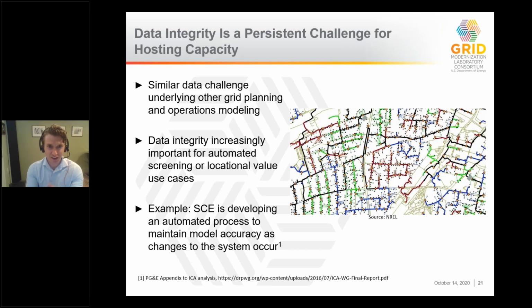I just want to flag how data integrity is really a persistent challenge for hosting capacity. This is similar to ADMS adoption or other systems that really rely on the system data being available and accurate. But as we think about the more advanced use cases of actually approving interconnection applications based on an automated method that maybe doesn't have somebody looking over the data and the analysis, this data integrity issue becomes even more prominent. There is an example of Southern California Edison developing an automated process for improving their accuracy and accounting for system changes, because the distribution system is very dynamic and changes all the time based on storms or upgrades or a number of other factors. Next slide, please.